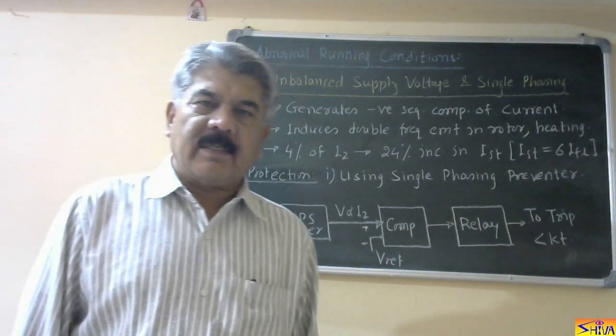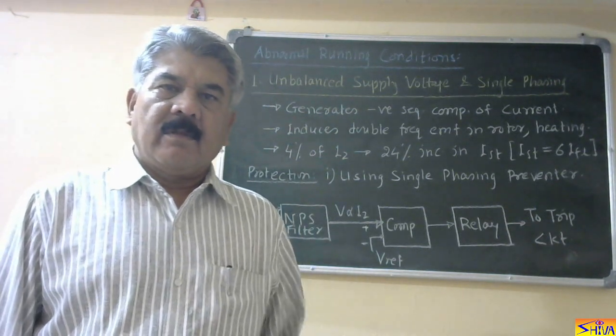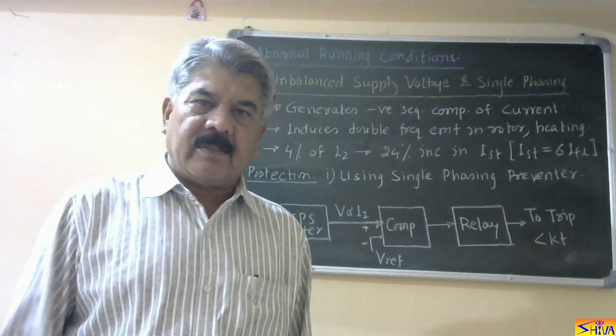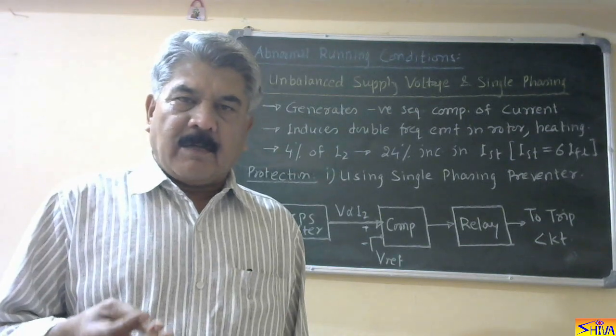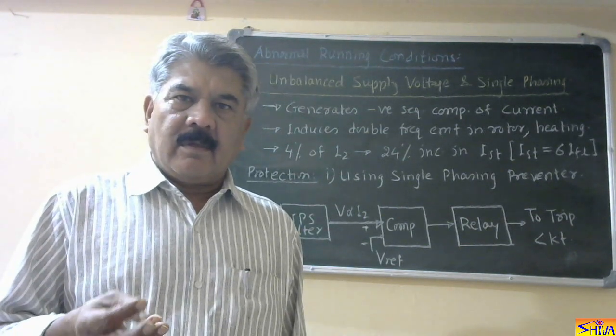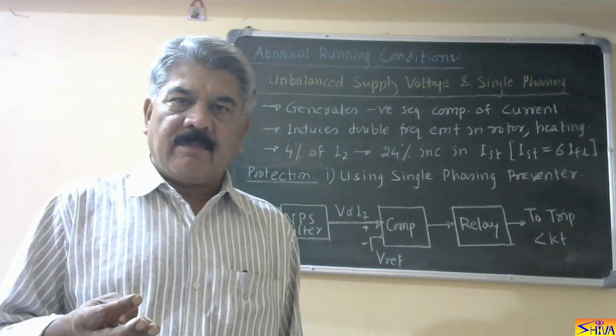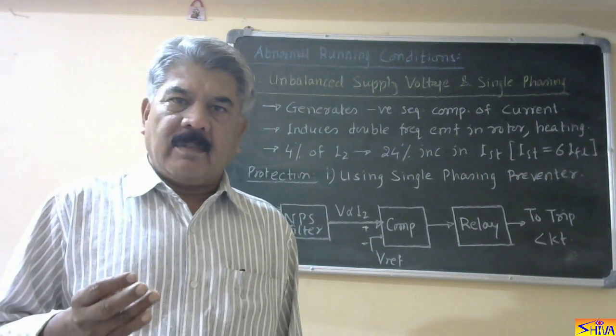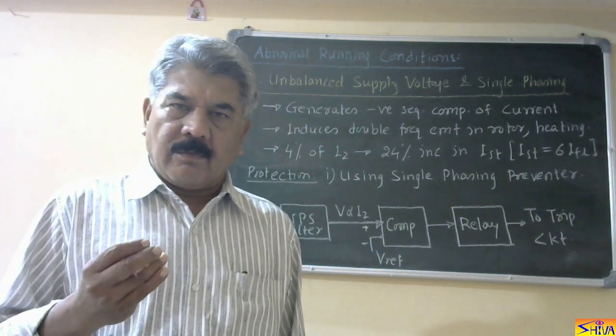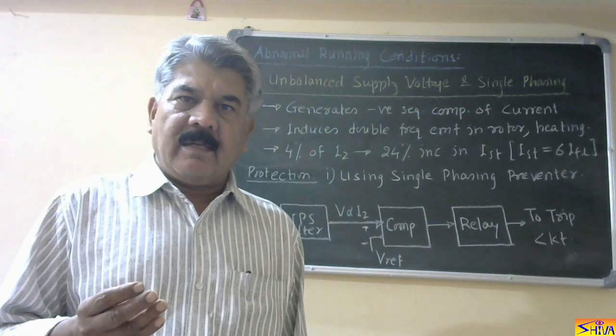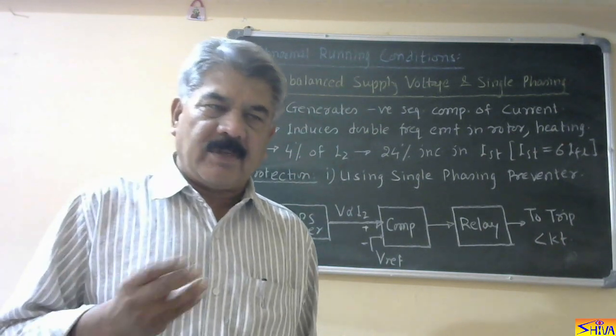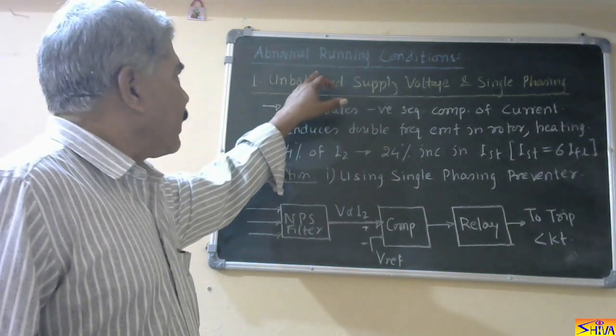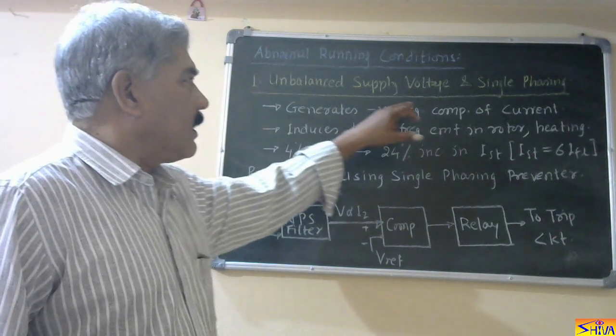Now I will discuss protection against a few abnormal running conditions. These conditions are unbalanced supply voltage, failure of one phase, then under voltage, then faults in the rotor, and then reverse phase sequence. So first I will discuss protection against unbalanced supply voltage and single phasing.